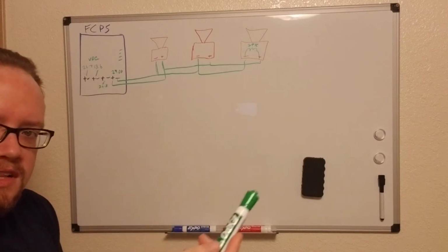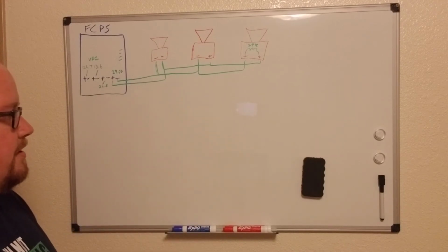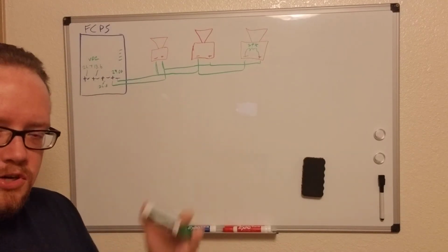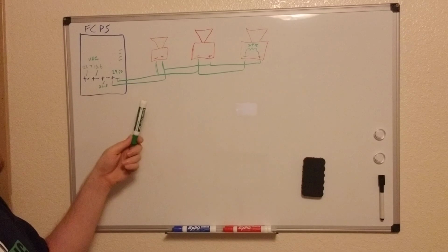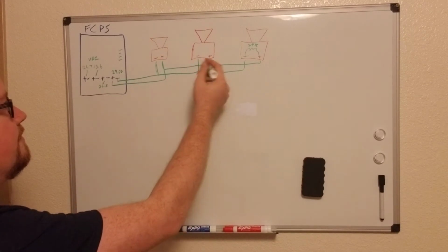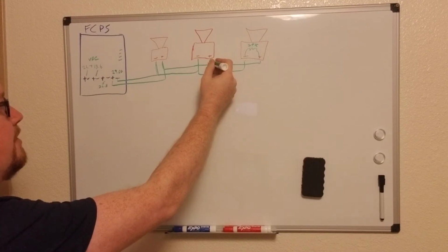And then you can mentally label it and maybe even put a label on that wire in the panel so they know which circuit goes where in the future, because you're probably going to be the one that's going to check it again, so it's going to save you time. But if you put your meter right there and you see 29 volts, oh, this is the open circuit. So now you can start looking for where that break is and try and reconnect it.